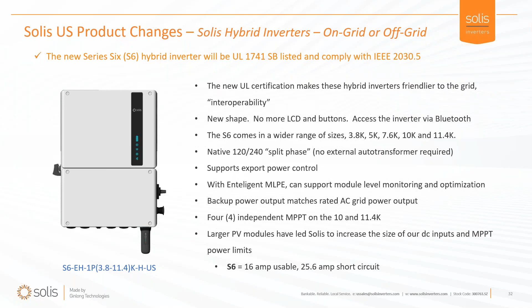Another really cool thing about this grid tie inverter is it can also operate off grid - it can literally operate without any grid at all. When you buy the inverter and set it up, originally it's set for self-consumption mode to maximize your solar kilowatt hours and, as a responsible citizen, reduce your carbon footprint. It's set up so the solar kilowatt hours you collect during the day first go to your loads, making sure your loads are covered, then they charge the battery, and then go to the grid.